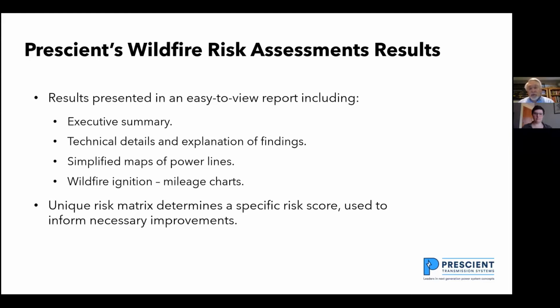So what we prefer to do is to actually walk down a power line, point out where the protection is on the line, point out where protection can be improved, point out things we've seen that could improve the construction of the line. And we use a risk matrix to determine a specific score.